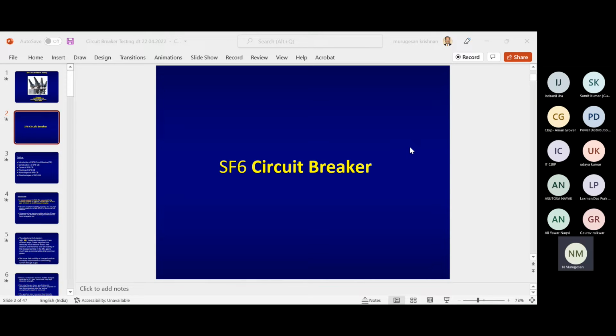Because the fault current will be in terms of kiloamps. What you carry is maybe 2000 amps, but the fault current will be in terms of 31K or 40K or 50K. Just imagine 50 times or 25 times the current flows. So what kind of destruction can it make? The whole circuit breaker will collapse.